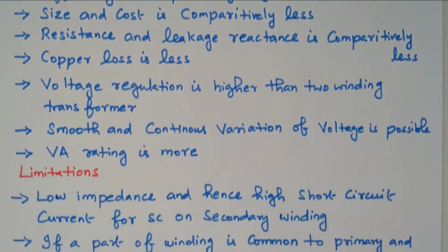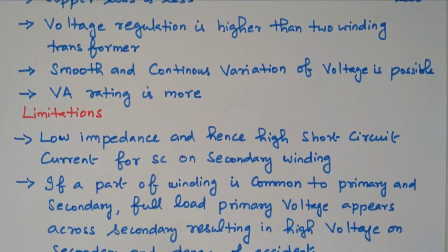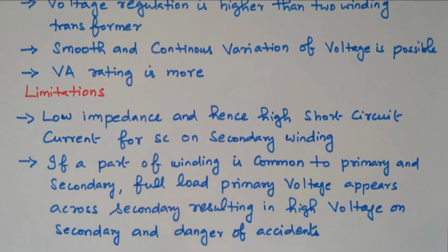Some limitations are available. The impedance is low, so hence there is a high short circuit current for a short circuit on the secondary winding, right? The impedance is very low. If we go for a short circuit, a large amount of short circuit current will flow through the secondary winding.